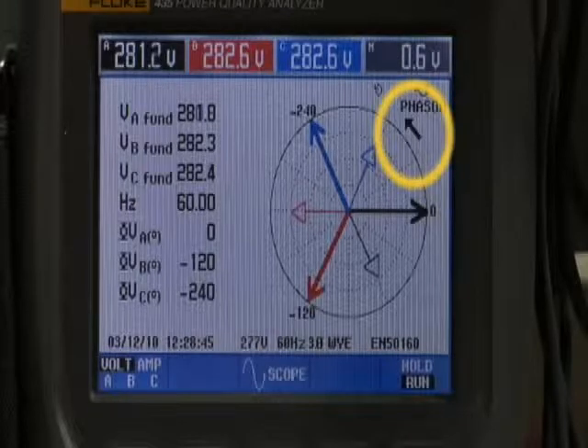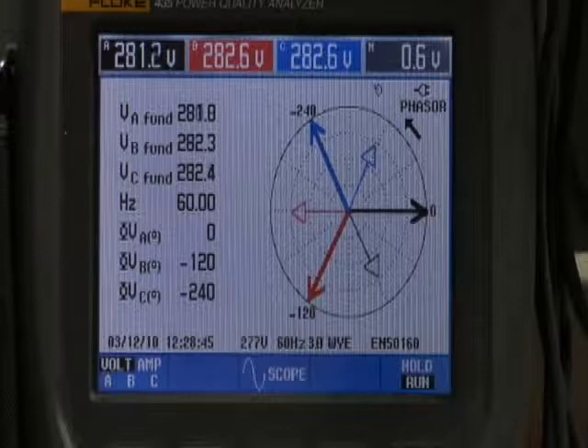Incorrect phase rotation. For normal phase A, B, C rotation, on the phasor diagram the arrow points in a counterclockwise direction. At the zero reference point, the thick black line indicates phase A voltage. Phase A current — the thin black line — can be seen lagging behind the phase A voltage. Phase B voltage is the thick red line at the 120-degree point, with phase B current as the thin red line lagging behind. Phase C voltage is the thick blue line at the 240-degree point, with phase C current as the thin blue line lagging behind phase C voltage.